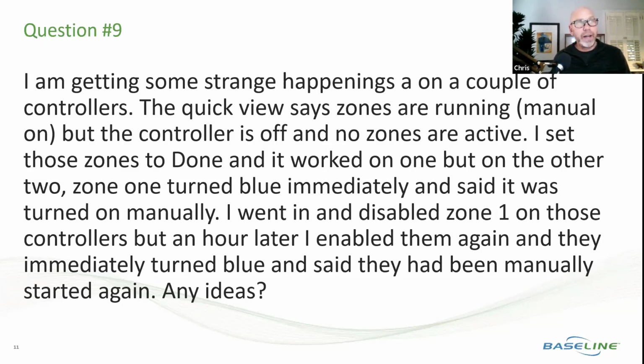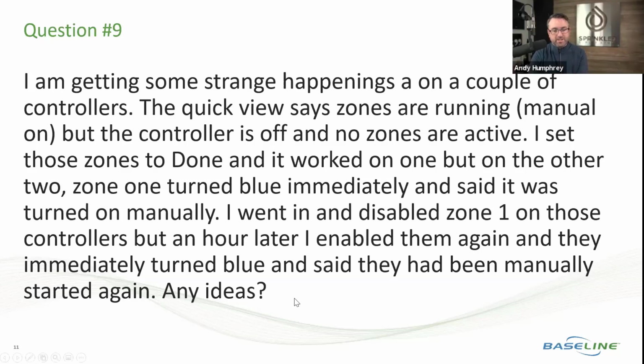After reading it, I would recommend checking what firmware version you are running on the controller, because we've got statuses that are in conflict. We had some status indications earlier in the year that were not consistent from controller to server because of server issues we were having, which have been rectified. So verify what firmware version that controller is operating on, then work with tech support to get to a resolution. That's typically one of the first things they do, so to save time, check your firmware version if anything wonky seems to be happening.